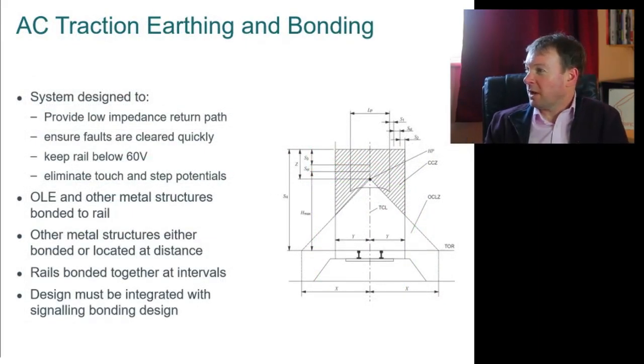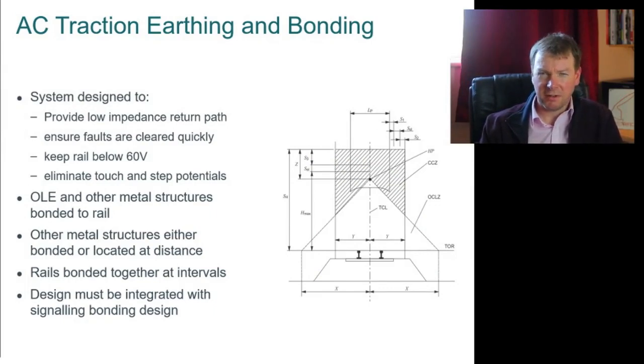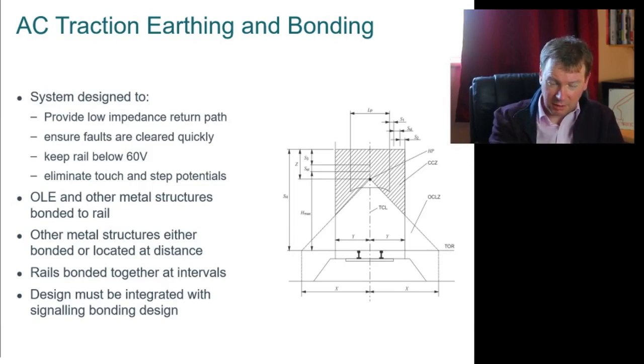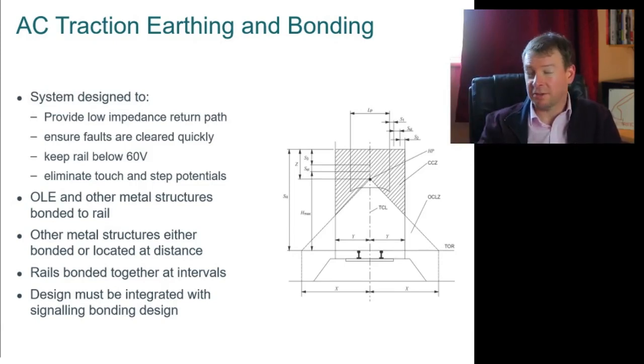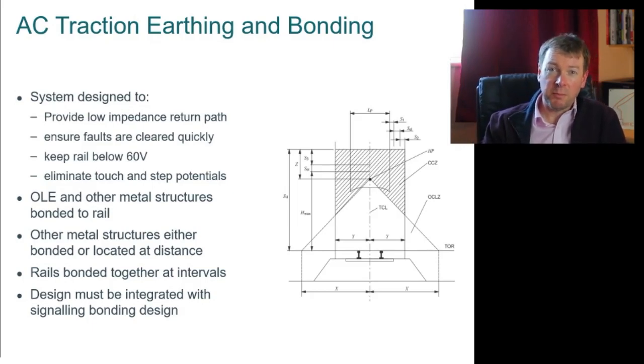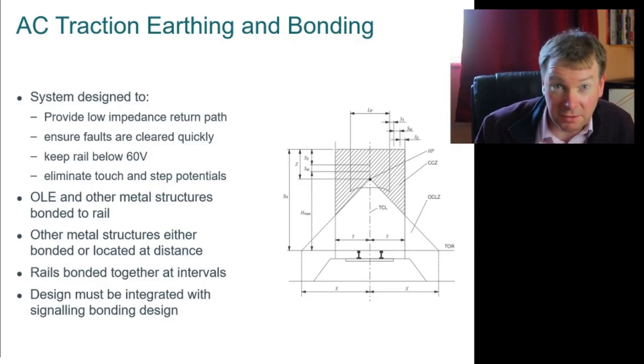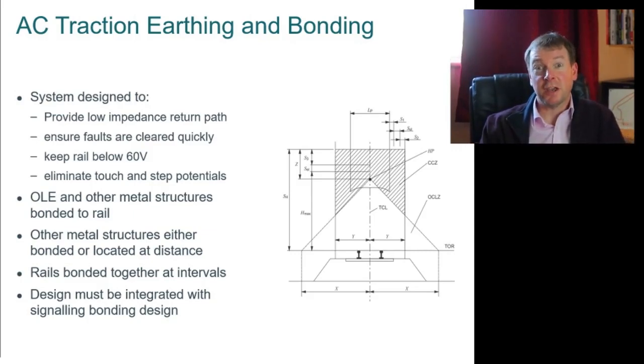Okay, let's talk about earthing and bonding. When you look at overhead line, you're really only looking at one half of the circuit. Those of you who know electrical circuit theory know a circuit has to have two halves - you send the current out to the load, then bring it back again. The overhead line is the outgoing half; the return half is equally important, and we design that return half, called earthing and bonding, to provide a low impedance, low resistance path back to the feeder station. That allows us to detect faults quickly and switch that power off before that 12,000 amps starts to do damage. It's also there to keep everything that's earthed below a safe voltage.